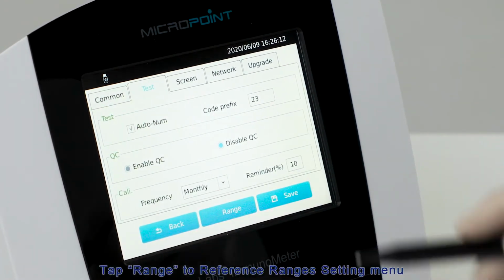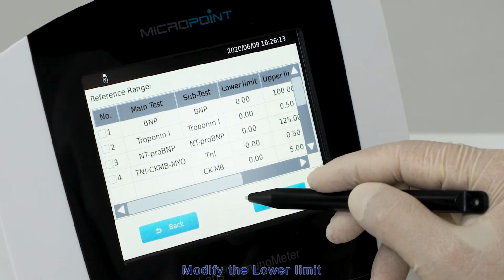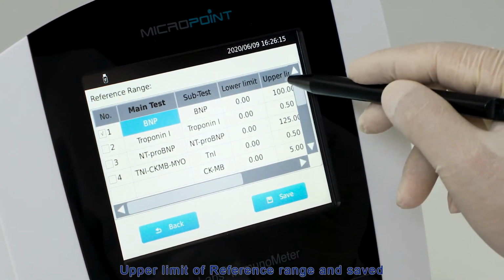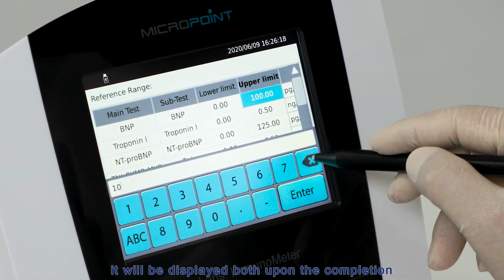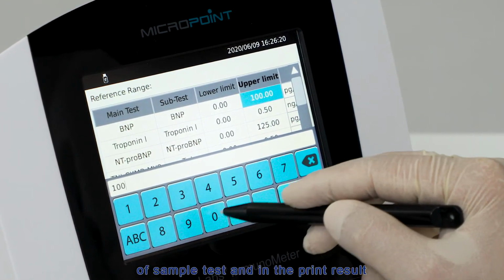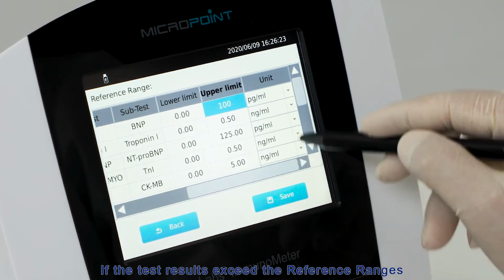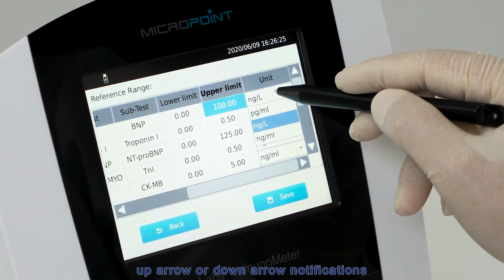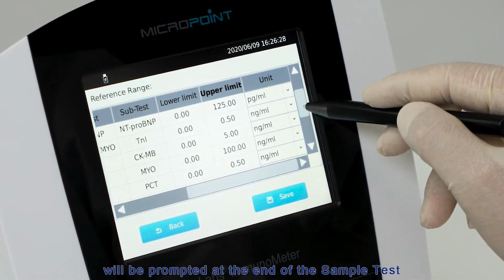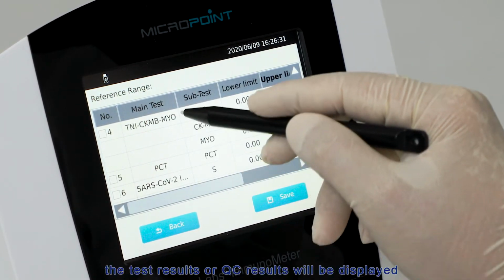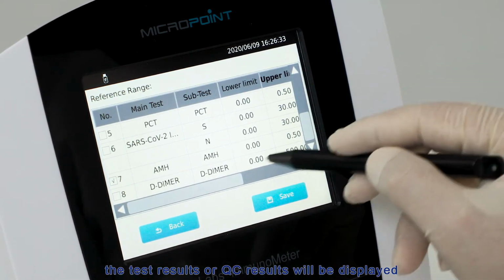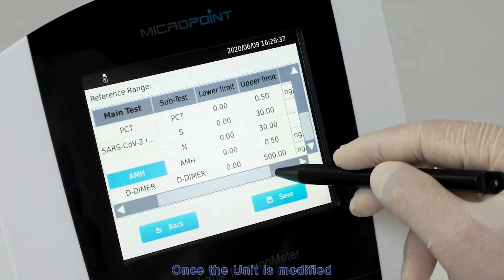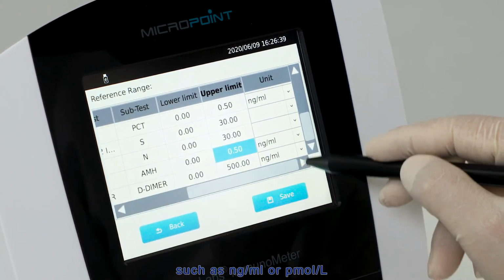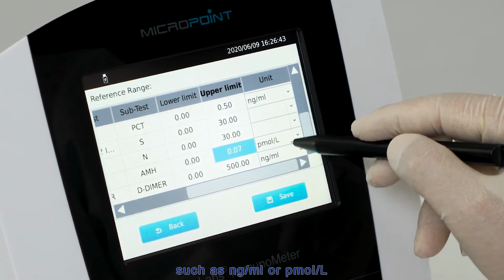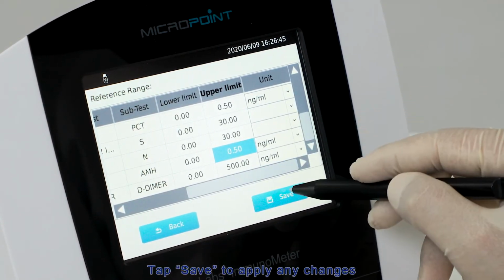Tap Range to open the reference ranges setting menu. Modify the lower limit, upper limit, and unit for each test item here. When the lower limit and upper limit of the reference range are input and saved, they will be displayed both upon the completion of the sample test and in the print result. If the test results exceed the reference ranges, up arrow or down arrow notifications will be prompted at the end of the sample test, as well as in the printout. The test results or QC results will be displayed and printed with such unit. Once the unit is modified, such as nanogram per milliliter or picomole per liter, tap Save to apply any changes.